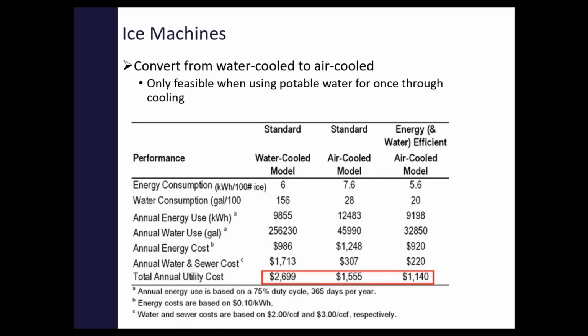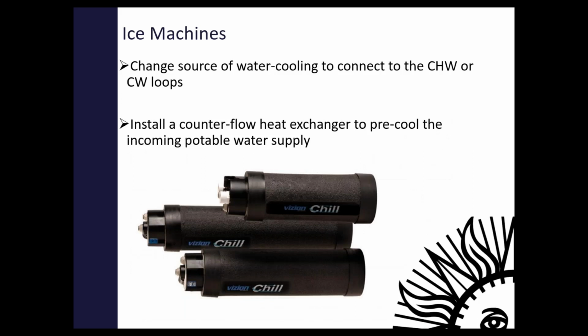Always, always, always check the connections going into your ice machine. If it's water cooled, it's almost guaranteed to be once-through water cooled, and that's a huge opportunity for savings. They usually have a constant flow, maybe 2 or 3 GPM going through them to provide cooling for the compressor. Instead, you can connect that to a chilled water loop or condenser water loop and provide cooling that way, so we're not having to waste the once-through cooling. We're just using chiller energy or another source of energy to cool. And you can also install these cool little counterflow heat exchangers, so when you have ice in the machine, it's continuously melting, so that's always going down the drain as about 32-degree water. So you can install this little heat exchanger to pre-cool the incoming water and effectively save a little bit of energy.